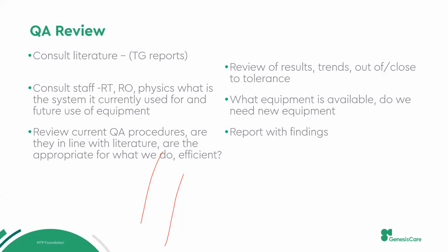Look at any QA program. We are straight away jumping into the basic tests which we are doing on a daily basis, right? We are not talking about any recommendations, consultation with the staff, because different departments have different needs. At the same time, you cannot develop your own things, right? You have to do an evidence-based practice. The first thing is definitely the literature review, what protocol says. If you are implementing a QA program in your department for LINAC, then definitely TG 142 is the right document.